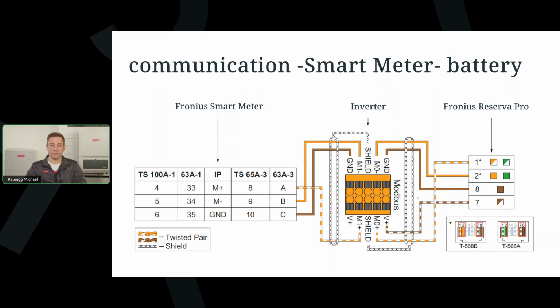So on one hand side, preferably in the Gen 24 Plus, you will unmantle the shield of the CAT cable and then bring it to our shield contact so that there are no electromagnetic interferences on the cable side. From then on, you can go on to the smart meter. So again, with the second Modbus port, Modbus plus, minus, ground, you can go on to the Fronius smart meter. And depending on the smart meter variant, you place these cables on the correct pins of the smart meter.